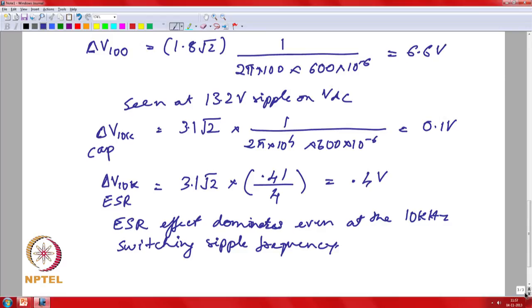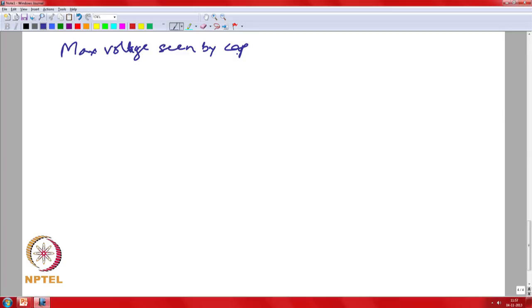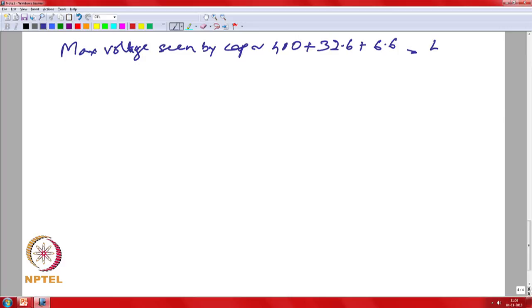Looking at the maximum voltage seen by the individual capacitors, assuming a worst-case scenario: you have 400 V nominal DC, plus 33 V from the 50 Hz effect, plus 6.6 V from the 100 Hz effect, giving about 440 V on the individual capacitor bank. You actually have a very tight margin of just 10 V, so your control has to be very effective to avoid large overshoots when dynamically controlling the DC bus.